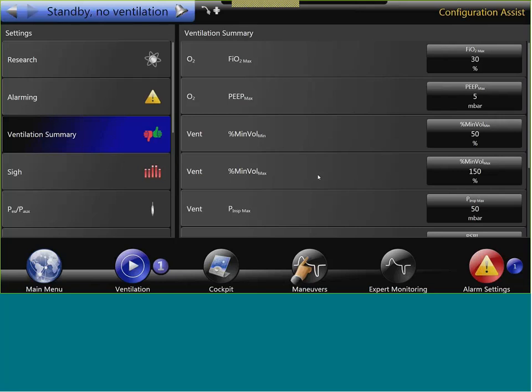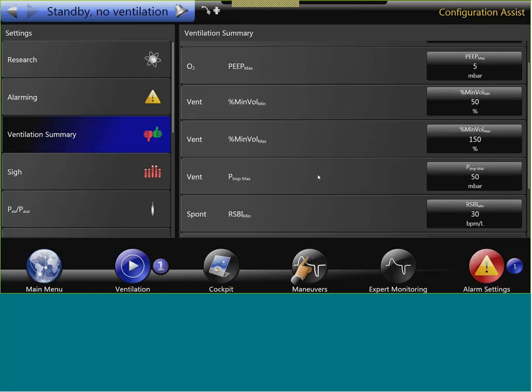This is up to the clinician to decide. But it will be very difficult if you set 150 here and the inspiration pressure is accepted at 50. So you will never get that timer to work. So this should be aligned. But I think this is sometimes a process, because most clinicians don't know about the concept of this minute volume. So this is maybe something they have to work with and get some experience.